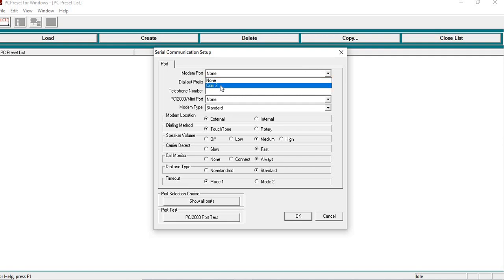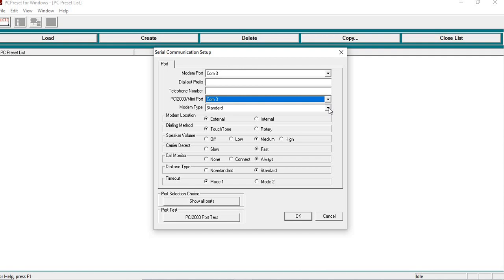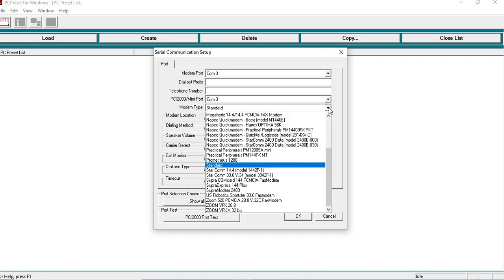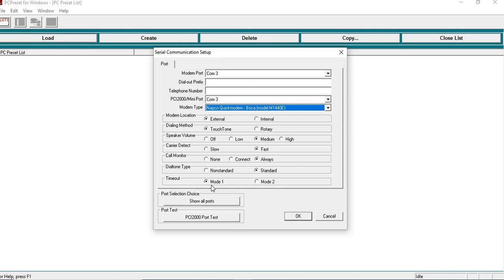So, modem port, COM3, since this picked up COM3, we're going to go in and we're going to change your PCI mini port, and then we're going to choose whatever NAPCO modem or whatever modem that we have. All these other features, it's external modem, you touch tone only, you definitely want to have. Speaker volume is just so if you're sitting there and you're just listening in the background, you can hear communicating with everything. Carrier detect is going to be on fast. Call monitor, I like always because it just lets you know what's going on. Dial tone type, standard, and then mode one, you want to go into it, and then you hit OK.